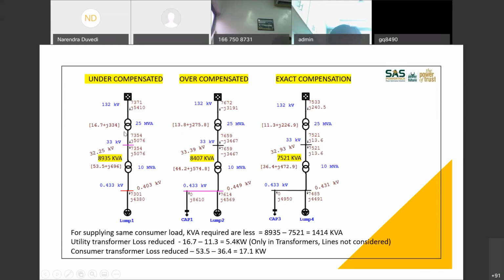Let's see what happens under these three conditions: undercompensated systems, overcompensated systems, and exactly compensated systems. I have tried to simulate a small substation and consumer. This 25 MVA transformer, let us say working at 132 kV primary, is from the utility company, and the 10 MVA transformer is at the consumer's end. The first thing, when reactive power is undercompensated, you can see that the load is drawing about 4380 kVAR. In this case, the kVA delivered by the utility are 8935. The utility transformer of 25 MVA has a loss of about 16.7 kilowatt, and the transformer at the consumer end is losing around 53.5 kilowatt as transformer loss.